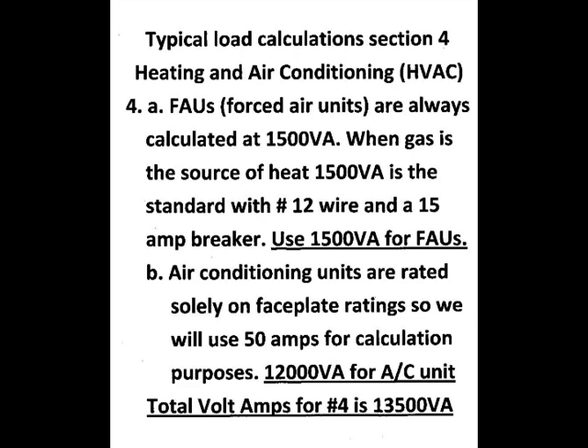The next thing we come up to is FAUs, or forced air units, which are always calculated at 1,500 volt amps when gas is the source of the heat. Air conditioning units are rated solely on faceplate ratings, so we'll just use 50 amps for calculation purposes — that's 12,000 volt amps for the AC unit. For the HVAC, which is the heating and air conditioning forced air unit, the whole package, we come up with 13,500 volt amps.